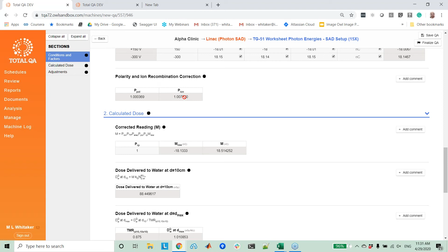Then it converts the raw reading to the corrected reading, which is the one you're actually going to use for the dose. Then it calculates the dose delivered to water at your chosen depth, typically 10. The TMR factor will have been pulled again from the machine for that energy, automatically, and then it calculates your dose delivered to water at Dmax. At that point you've got a choice. If you're not going to do an adjustment, you can say no, I'm not doing an adjustment, and this last section will disappear, and you can finalize from that point.